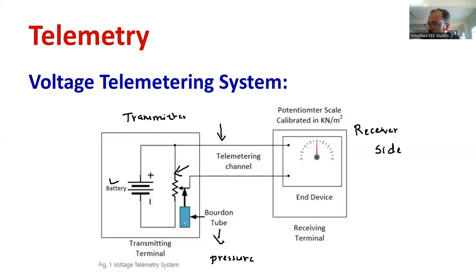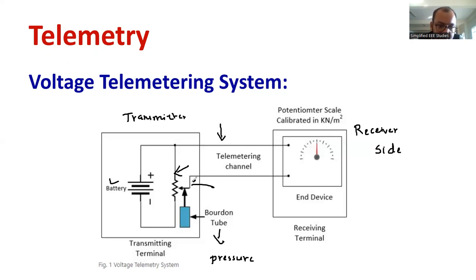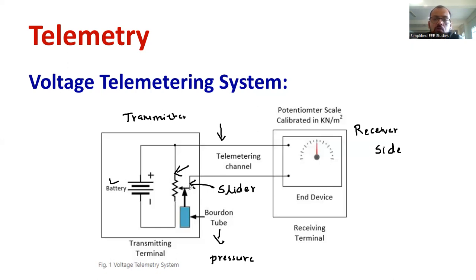How does it work? As we can see, the potential divider works based on the voltage division rule or voltage division formula. With respect to the input of the Bourdon tube, the position of the slider will be changing. This is your slider of the potential divider. As the pressure changes, there is a change in the Bourdon tube, and the Bourdon tube is connected with the slider, so the slider position also changes.